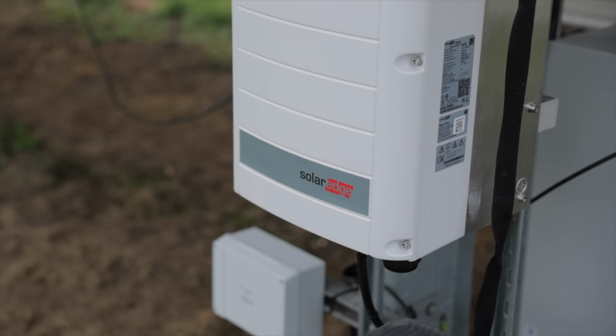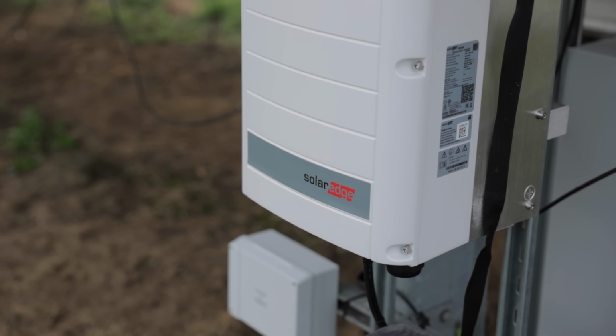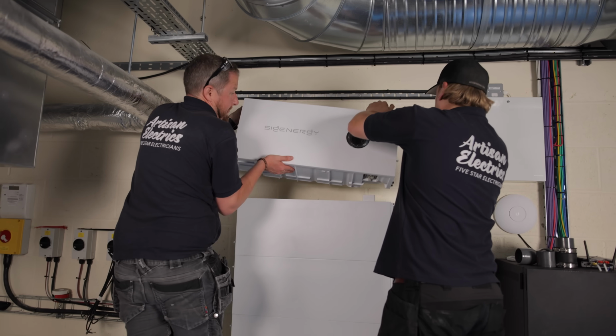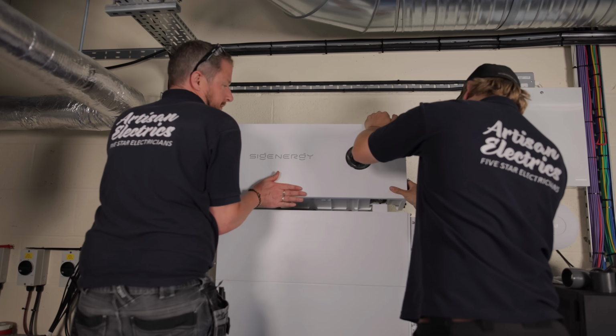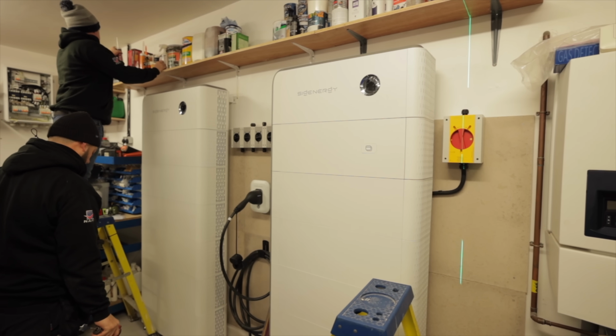Now, the other element to this is the inverter size. So no matter how many batteries you have, how much capacity you have and what the C rating is, the inverter is the bottleneck. The inverter is the limiting factor. So if you've got, say, 100 kilowatt hours of battery storage with a 1C rating, that doesn't necessarily mean that your battery system can charge and discharge at 100 kilowatts. It will be limited by whatever inverter is sitting there at the top of the stack of batteries, or however your battery system is configured.